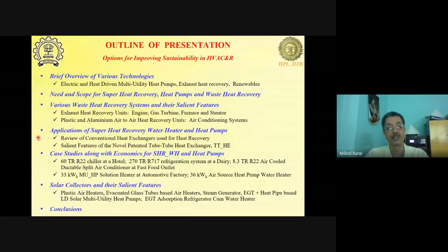Now, for applications like superheat recovery, we will take a review of the conventional heat exchangers and the novel heat exchanger, which is based on tube-in-tube configuration, which offers several advantages. So we'll see what the salient features of that are, and how that has offered a very reliable heat exchanger for this particular application. Some of our heat exchangers have operated for over 11 years without a single service call.